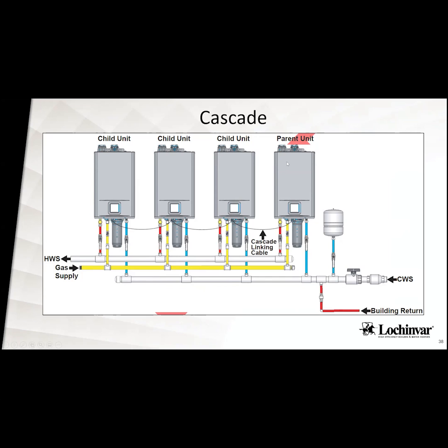So whichever unit is the primary unit is the unit that the internal pump is going to run off of. So if you have 4 set up like this, and this unit right here is in that first position, then the recirc will be running through that unit. Every 8 hours of burn time, it's going to switch off which one's primary, secondary, third, and fourth. So if this unit here jumps into being the secondary unit, then that pump will kick on, and that will be the pump for the system until this unit becomes the primary. So you're getting even usage through all of the units and the pumps through all of those units as it is cascading back and forth between the units. Does that make sense?